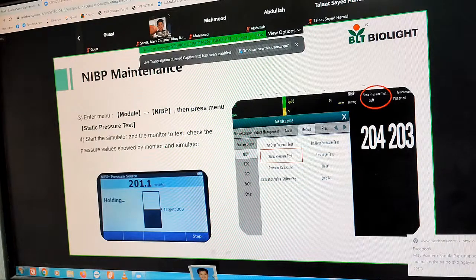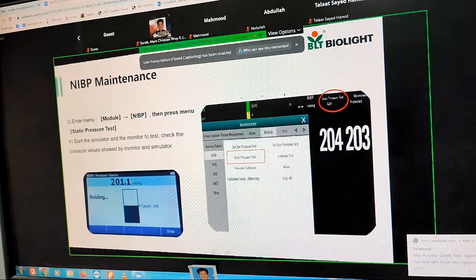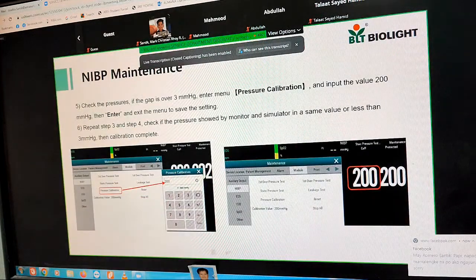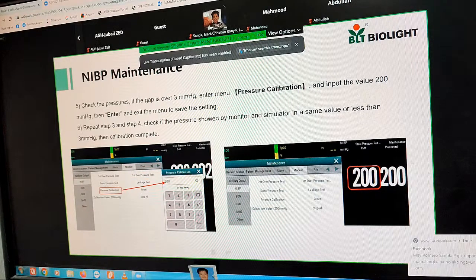Start the simulator and monitor to test, check the pressure value shown by the monitor and simulator. You will get two values and need to compare them. If the gap is over 3 millimeters mercury, enter menu Pressure Calibration and input the value 200 millimeters of mercury, then enter and exit the menu to save the setting. Repeat these steps to check if the pressure shown by the monitor and simulator is the same value or less than 3 millimeters mercury difference. Then calibration is complete.